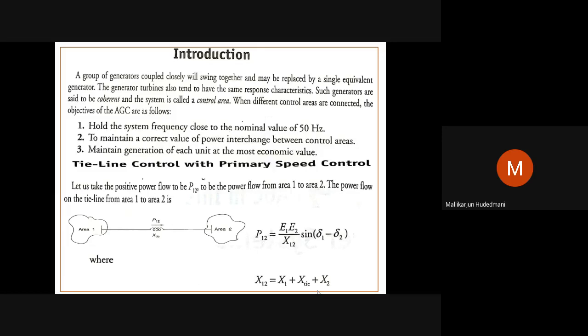When I have an interconnected mode of operation of a power system, definitely power flow occurs bidirectionally, 1 to 2, 2 to 1, as and when there is a need for flow of power from one to another. This example shows P12, which means there is a specific flow from 1 to 2 only, which is given by the sine of the angle delta 1 minus delta 2. If delta 1 is leading with respect to delta 2, we say power flow occurs from area 1 to area 2. That's the reason the arrow is mentioned from area 1 towards area 2. It is mentioned as P12.